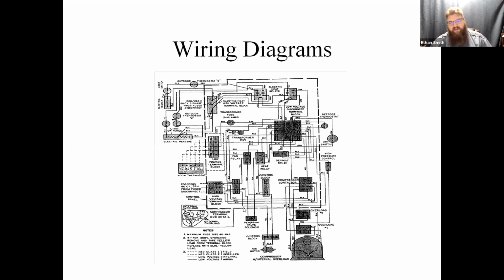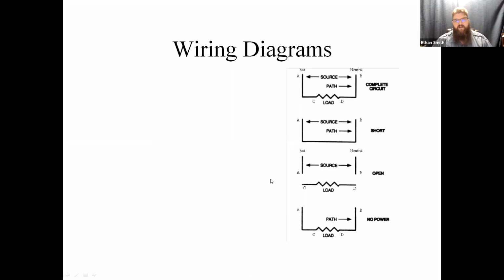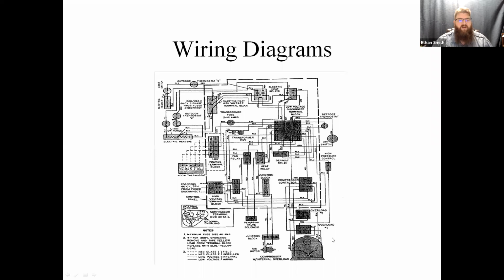Okay. But that being said, let's dive into wiring diagrams here, guys. So this is a type of wiring diagram called a pictorial wiring diagram. It shows your components and then shows what they are electrically inside them. This is kind of a wiring diagram that's fallen out of favor in the last 20 years. But you used to see this a lot on older equipment. They'd have a picture of the device and then a description of how it worked electrically. They were really nice for some things, in that you could see generally what your equipment looked like, what the device should be shaped like, what you're looking for. But they were kind of a pain in the butt for diagnostics because they weren't very linear.